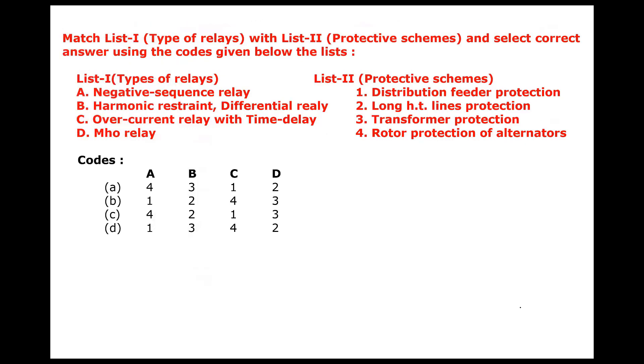Match the following again. Negative sequence relay — where do we use it? For rotor protection of alternators. Harmonic restraint differential relay is used in transformer protection. It is a differential relay with an additional harmonic restraint feature to prevent nuisance tripping or mal-tripping during inrush currents.